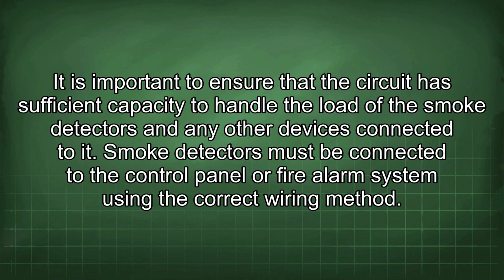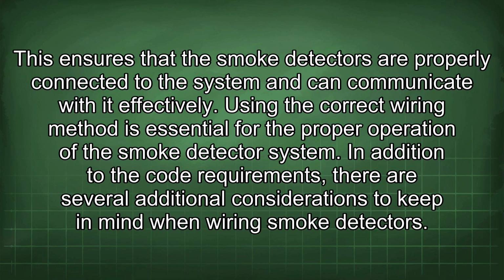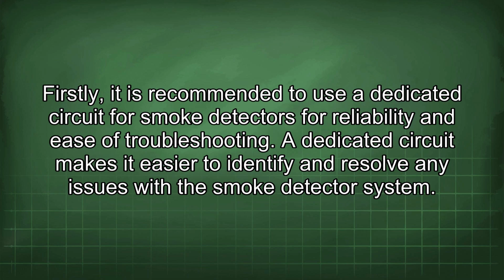Smoke detectors must be connected to the control panel or fire alarm system using the correct wiring method. This ensures that the smoke detectors are properly connected to the system and can communicate with it effectively. Using the correct wiring method is essential for the proper operation of the smoke detector system. In addition to the code requirements, there are several additional considerations to keep in mind when wiring smoke detectors. Firstly, it is recommended to use a dedicated circuit for smoke detectors for reliability and ease of troubleshooting. A dedicated circuit makes it easier to identify and resolve any issues with the smoke detector system.